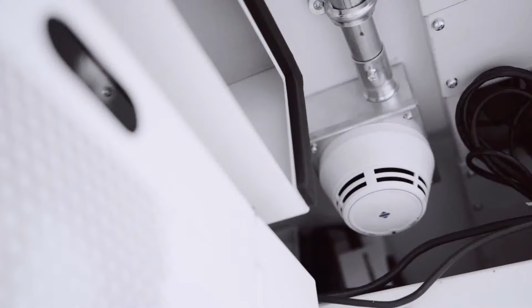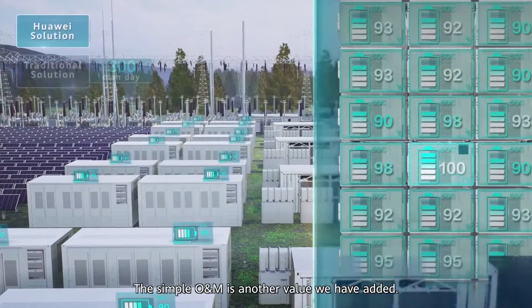In a traditional energy storage system, one central PCS manages more than 2,000 battery cells. As these cells are connected in parallel and series, internal differences cause cell mismatch. A centralized cooling system worsens this mismatch due to uneven working temperatures, leading to reduced usable capacity, quicker battery degradation, higher O&M costs, and lower safety.